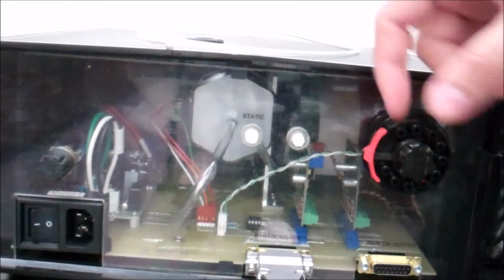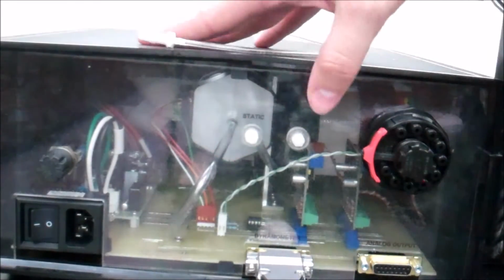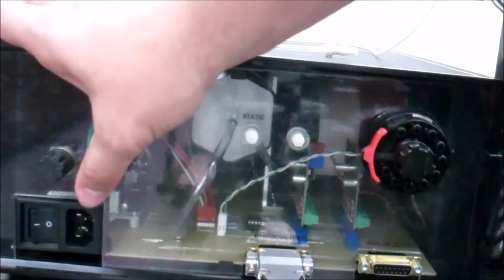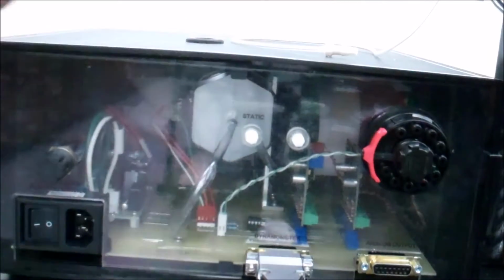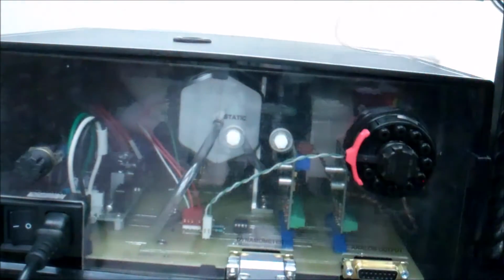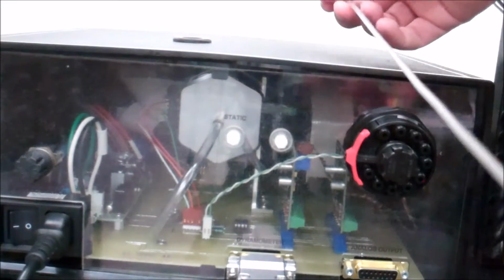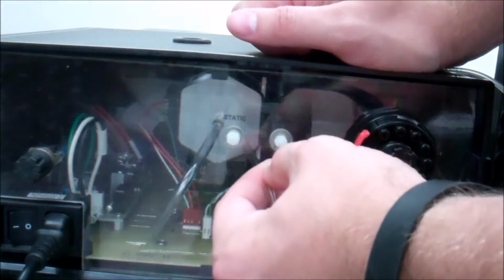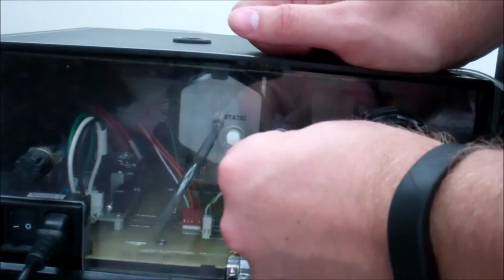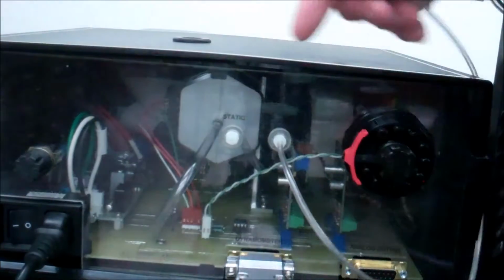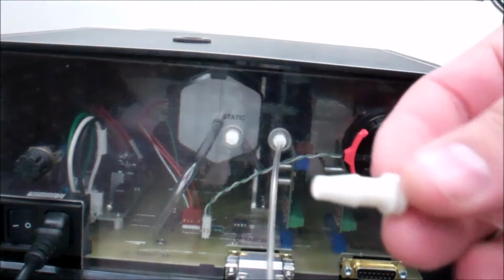When calibrating the pressure transducer, if you look on the back of it, there's a total, a static, and the connection for power. So you're going to go ahead and connect the power. Then you're going to want to connect the small tubing to the total barb. Then you're going to connect the other end of this to the manometers that we use.